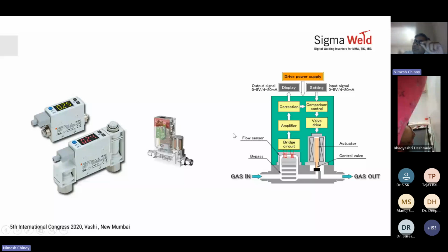You can set the value that you want. If it goes above or beyond that value, it will become a red indication that you are below or you are out of range. Then you have a needle adjuster on this digital flow meter, which will allow you to adjust the flow as well, to get the right flow. So not only measure, but control as well. So this is called a digital flow switch. And this gives you output in terms of 0 to 10 volts, 4 to 20 milliamps, or you can get ones with a LAN cable as well. It will give you a 485 signal and you can access the parameters within it.